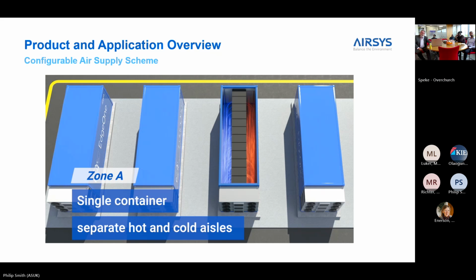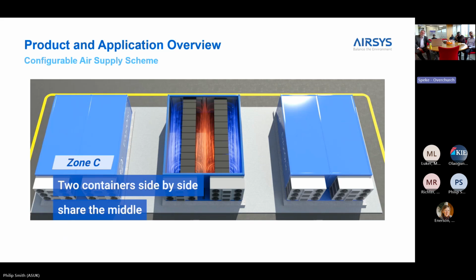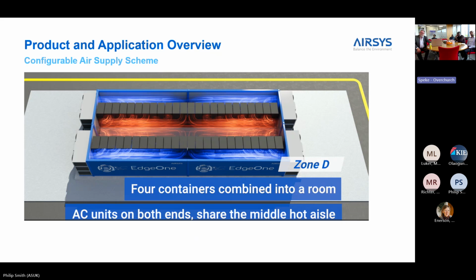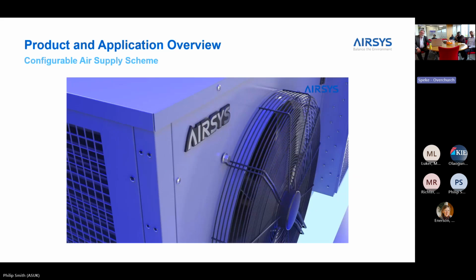And as I say, you can zone them, make them bigger, combine them. Essentially, if you've got a warehouse that's a data center, you can put these products along the outside wall and create banks of cooling that align with the cold aisle contained racks inside. So it becomes a very efficient system as long as you've got the facility to get that fresh air into the room. Okay.